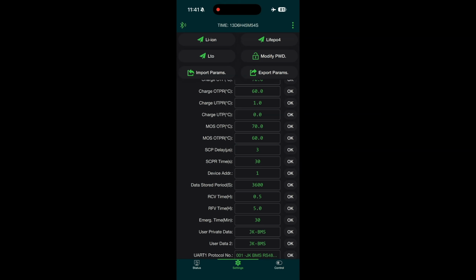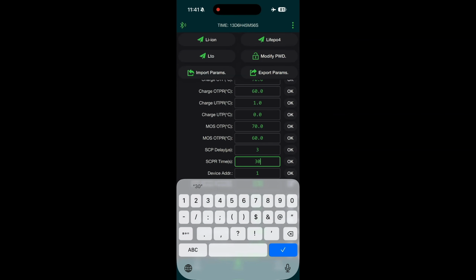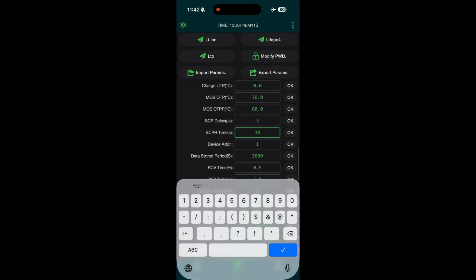SCPR stands for Short Circuit Protect Reset. So it'll wait 3 microseconds to disconnect for a short circuit. Okay, but then how long do you want the BMS to wait until it will allow the BMS to again receive discharge or charge? Okay, I've got this set to 30, which I think is fine.